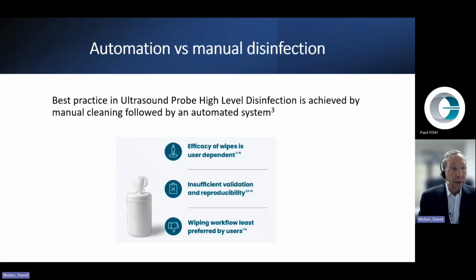Automation versus manual disinfection. Best practice in ultrasound probe high-level disinfection is achieved by manual cleaning followed by an automated system. The efficacy of wipes is user dependent. It's easy to miss spots on a probe just using wipes. In addition, if the wipe dries out, it doesn't have adequate chemical disinfection. With the use of wipes there is insufficient validation and reproducibility, which has been shown. And the wiping workflow is the least preferred by actual users of ultrasound probes.